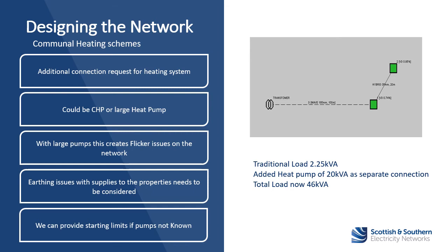It's always worth getting in touch with us to discuss that, because we can provide you the limits, but we need to make sure it's not going to affect the network or cause any issues on startup. We'd always encourage you to get in touch with us if you're looking at a communal heat pump or CHP unit, to see what the best solution is going to be. One thing to also consider with communal heating systems is the earthing, because we don't want cross-bonding between connections for the electricity supply. We need to make sure that's all safe as well, so that's a consideration there.